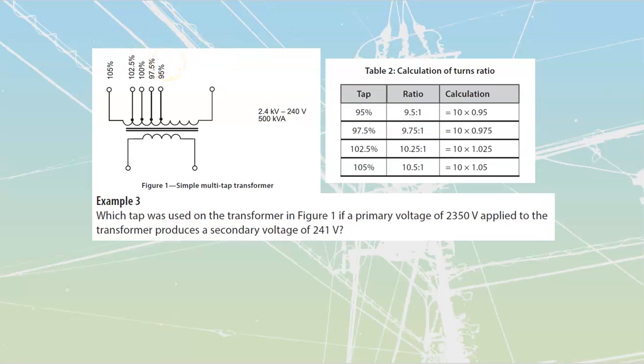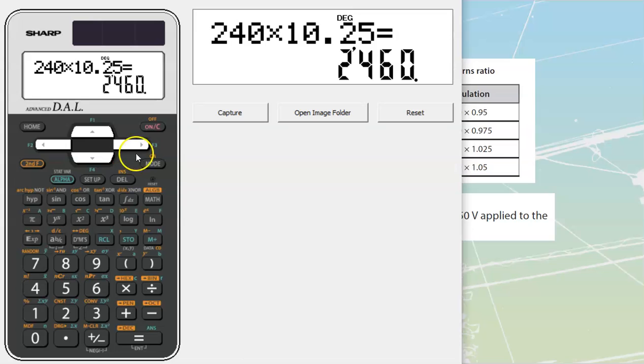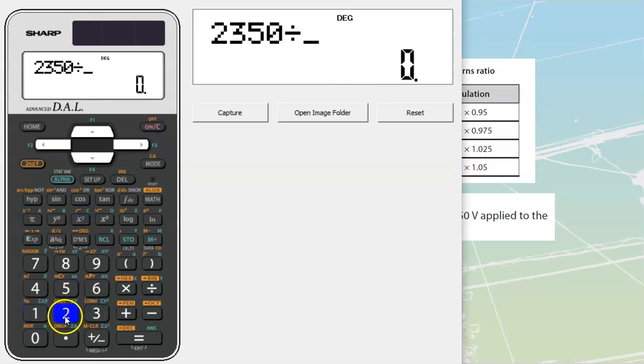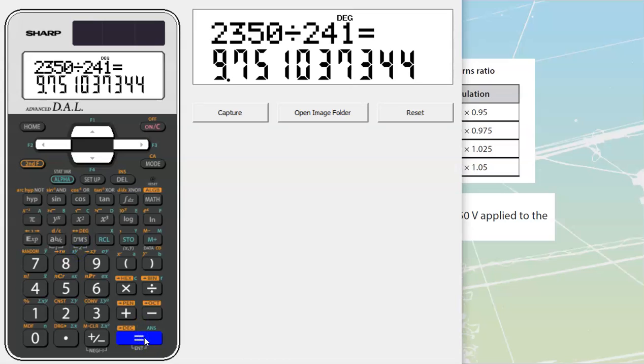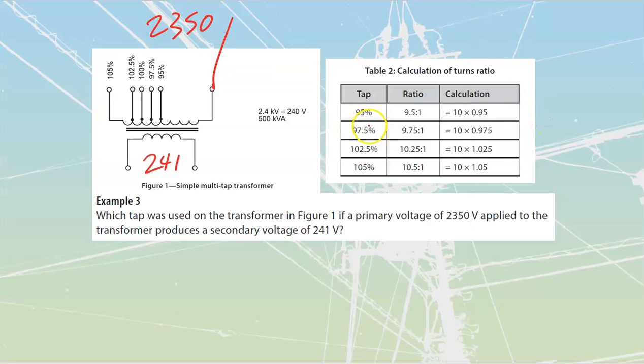That's backwards thinking. Example number 3: which tap was used on the transformer in figure number 1 if a primary voltage of 2350 applied produces a voltage of 241 on this side? I don't know, but we could just take 2350 divided by 241, and that will tell us what the ratio would be. 2350 divided by 241 is equal to a 9.75 to 1 ratio. So if it's a 9.75 to 1 ratio, we would have had to be using our 97.5% tap over there.